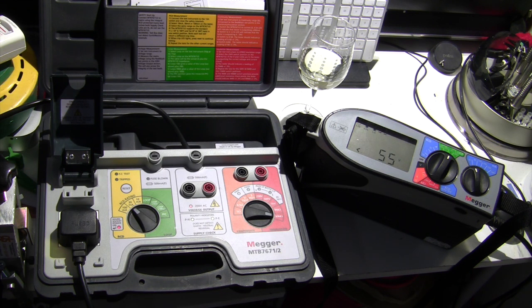This is a 32 amp type B 60898 ring, 2.5, 1.5, the usual nonsense, and the upper limit for that, according to the regs, is 1.10 ohms. I'd expect to see a number below 1.10 ohms if I was doing a normal loop test from a socket outlet on this circuit. Like I say, I'm on the end of an extension lead, so it's going to be higher than the 0.79 or whatever I normally get on this circuit. It's going to be some way higher than that. It's quite a thin extension lead actually, it might even be significantly higher than that.